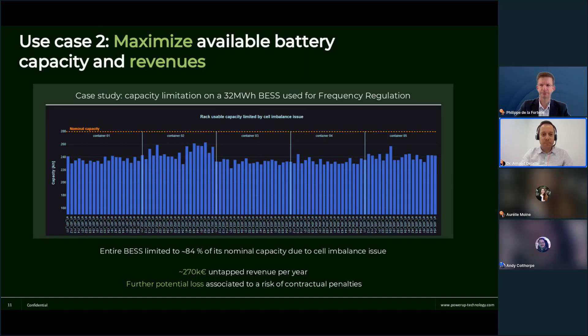The explanation is that cell imbalance is effectively a source of battery degradation that can lead to thermal runaway in the long term, but it can also introduce immediate performance issues. Once we detect such cell imbalance and unavailable capacity, it can sometimes be resolved either by a cell balancing procedure or by replacing the limiting module, depending on the root cause of the cell imbalance.